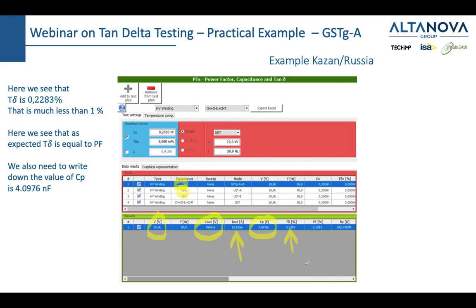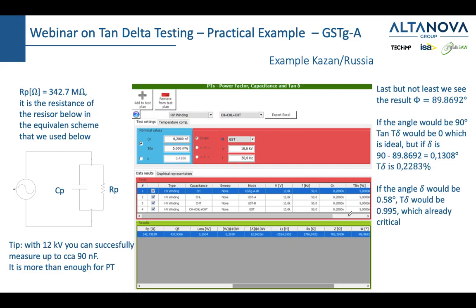So moving on, we also have this RP. So we will see that on the next slide. RP is 342.7 megohms. So actually, when we executed this measurement, we measured the capacitance of 4.097 nanofarad and we measured the resistance of 342 megaohms. So we have these two values, and if you take these two numbers and use the formula for tan delta, which is equal to 1 divided by omega RC, you would get 0.2283 of tan delta.